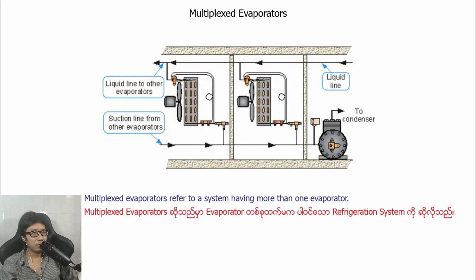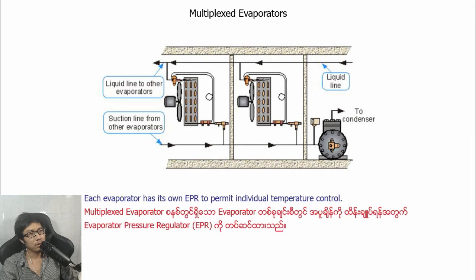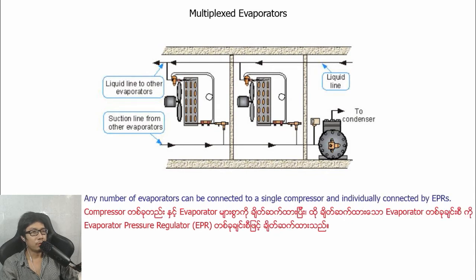Multiplex evaporator. Multiplex evaporator refers to a system having more than one evaporator. Each evaporator has its own evaporator pressure regulator, EPR, to permit individual temperature control. Any number of evaporators can be connected to a single compressor and individually controlled by EPR.